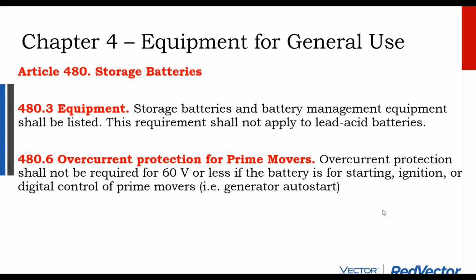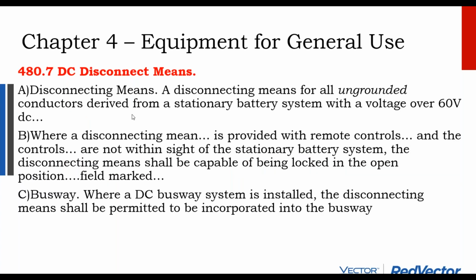get batteries that have built-in controllers. These controllers can get quite advanced. These controllers often will already have fuses and relays built into them for protection from overcurrent. So adding external overcurrent protection can be redundant. At this time, it's not necessarily a mandate for these battery circuits to have overcurrent protection if they otherwise are not required to have overcurrent protection.